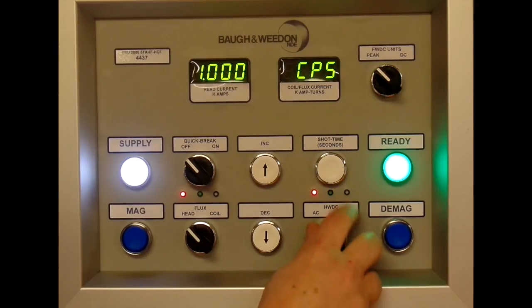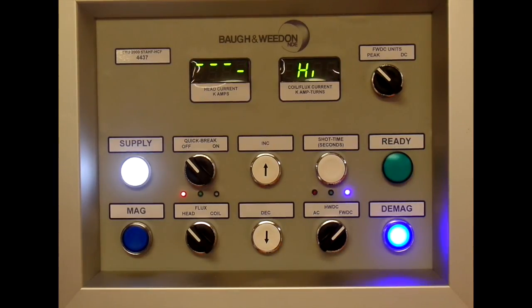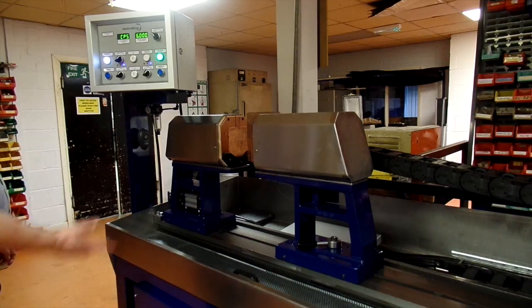The only one that's different is the full wave. We do a shot, and now we do a demag, which takes much longer — performing multiple shots through the demagnetisation cycle.